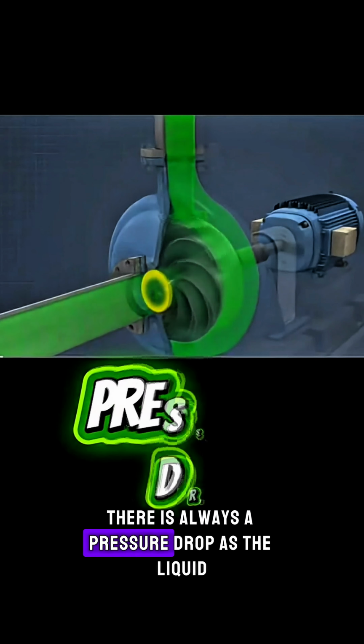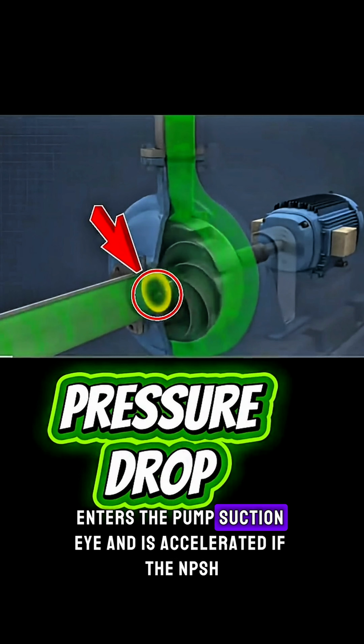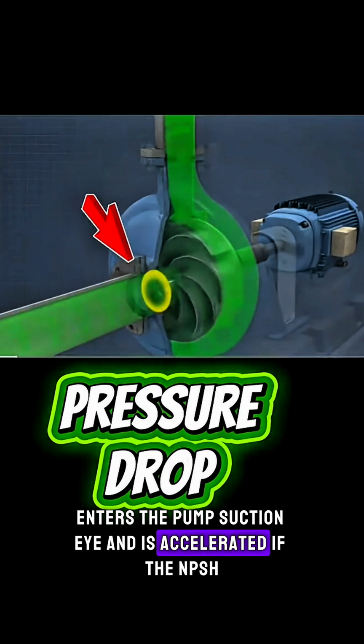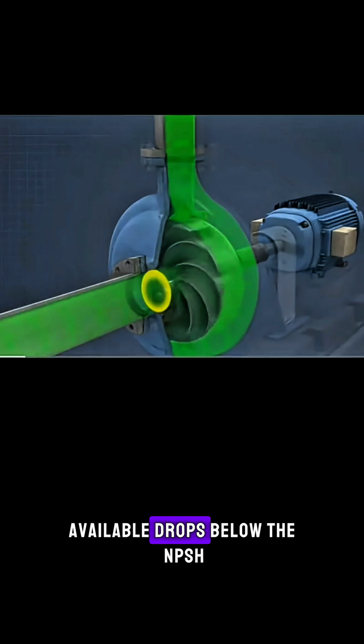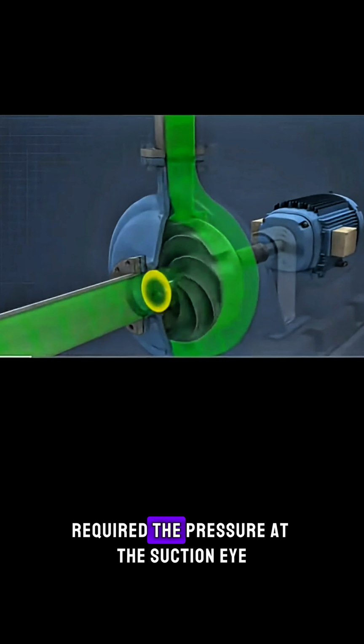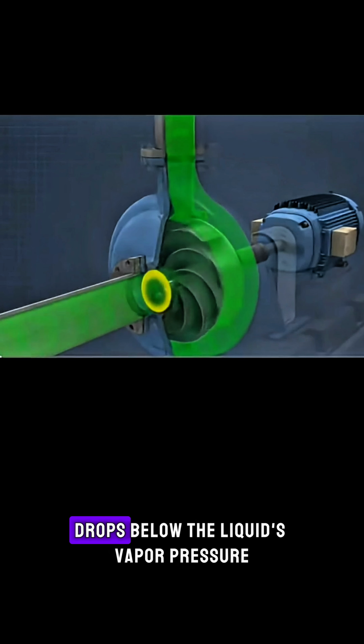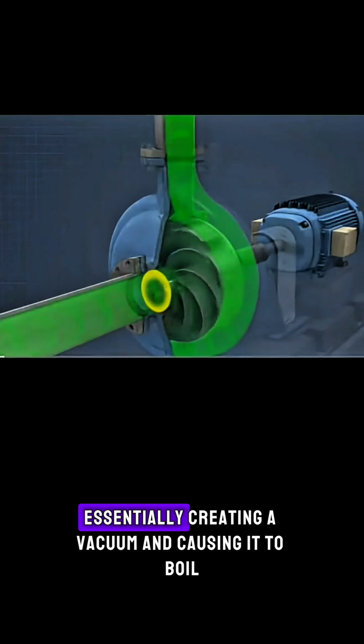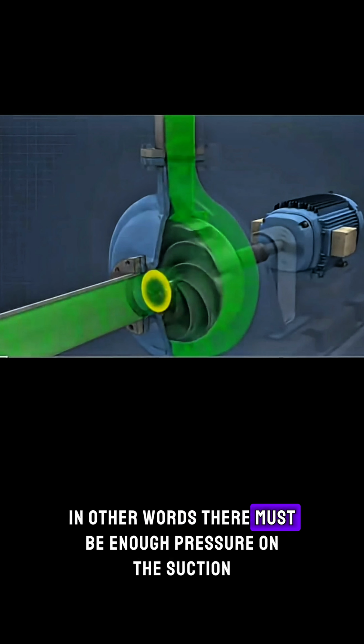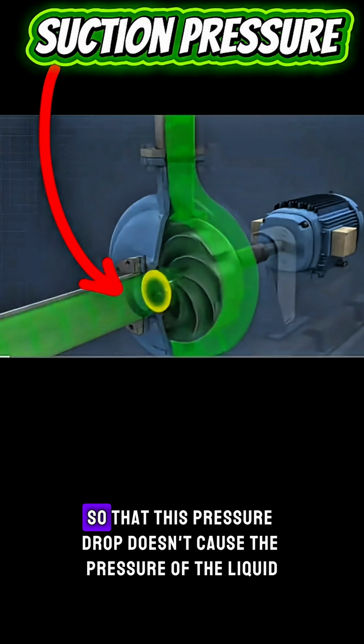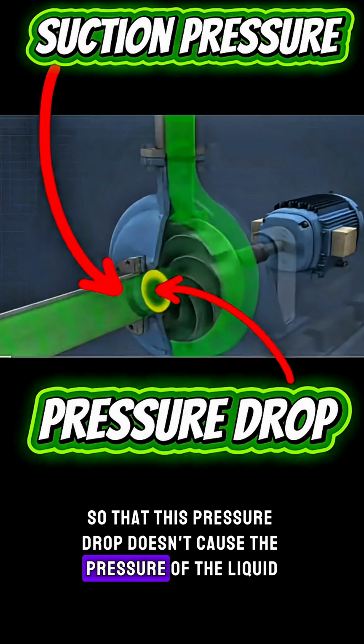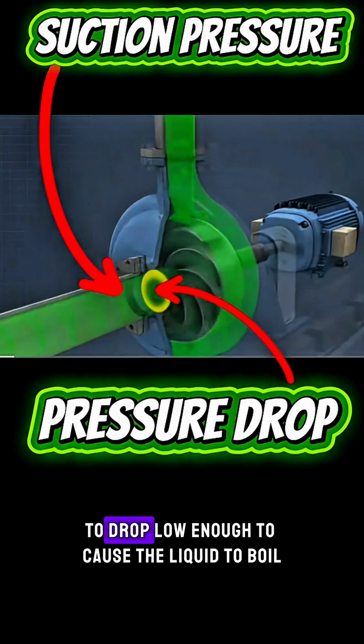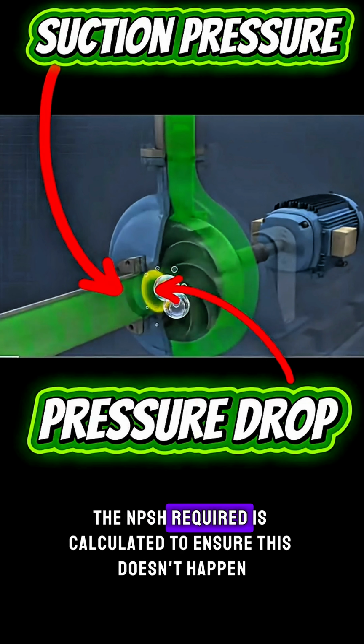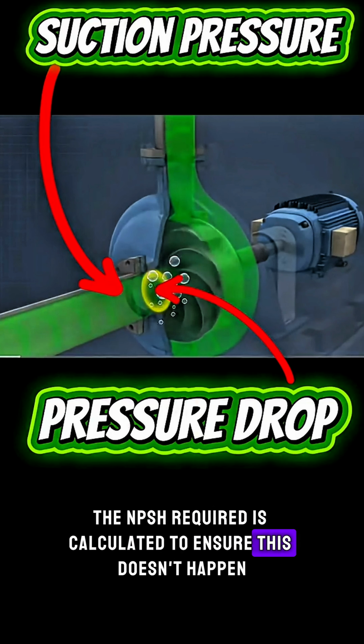There is always a pressure drop as the liquid enters the pump suction eye and is accelerated. If the NPSH available drops below the NPSH required, the pressure at the suction eye drops below the liquid's vapor pressure, essentially creating a vacuum and causing it to boil. In other words, there must be enough pressure on the suction so that this pressure drop doesn't cause the pressure of the liquid to drop low enough to cause the liquid to boil. The NPSH required is calculated to ensure this doesn't happen.